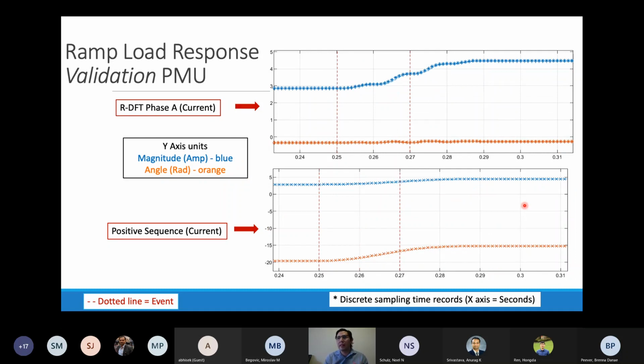Here I'm testing the same case scenario, but with a ramp load. Again, I'm testing the recursive DFT in phase A and the positive sequence. As we can see, our ramp happens between 0.25 and 0.27 seconds. After this, we need a cycle in order to be able to reach a steady state. And in the positive sequence figure at the bottom, we can see how our signals look better, and also we can have this earlier detection.